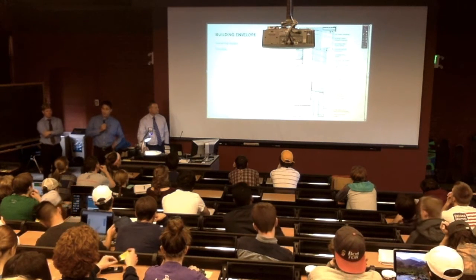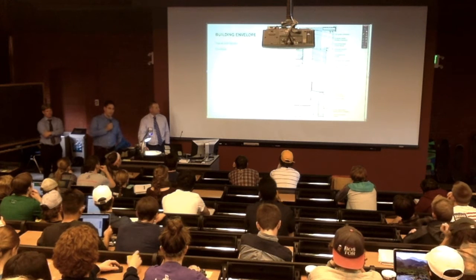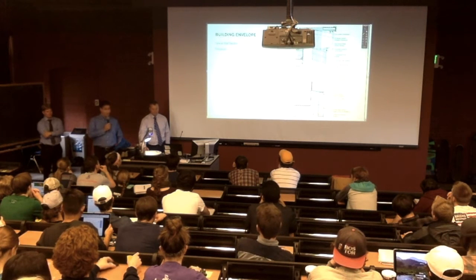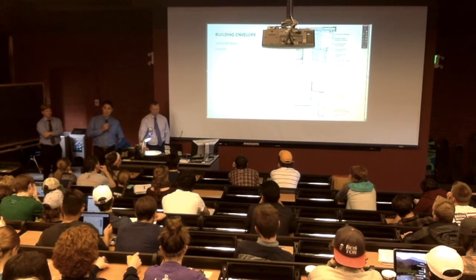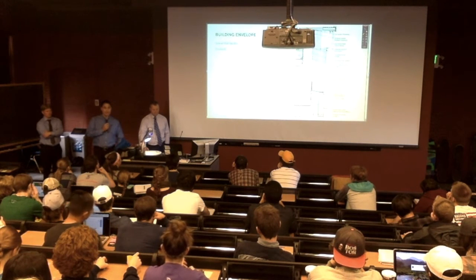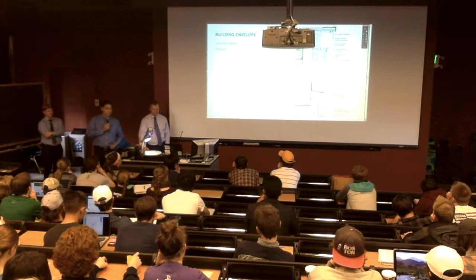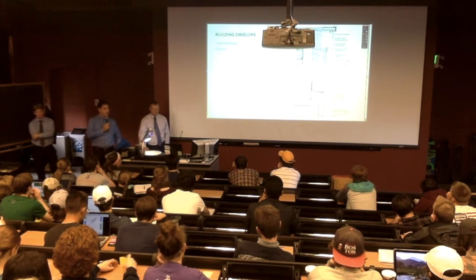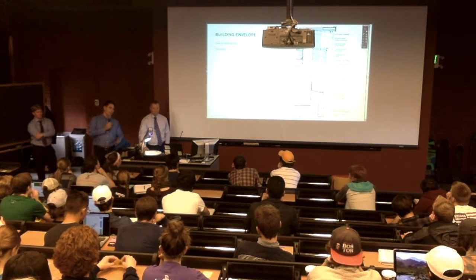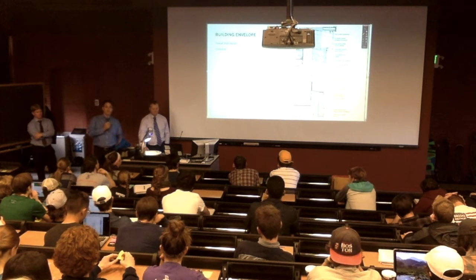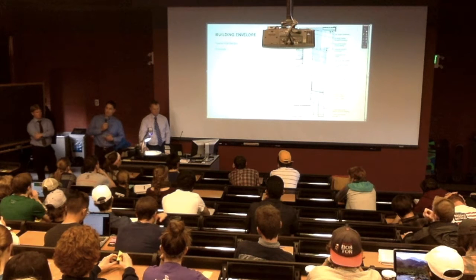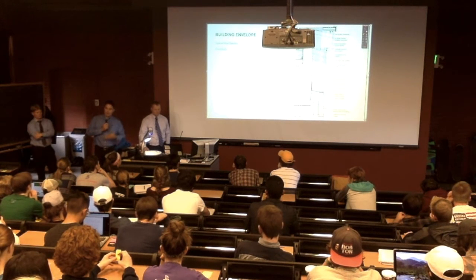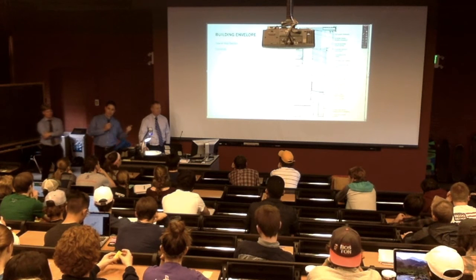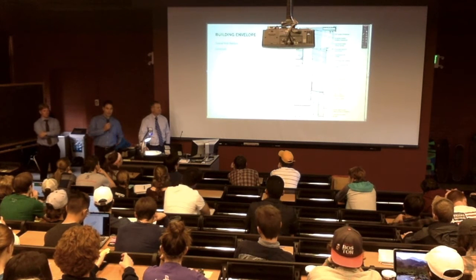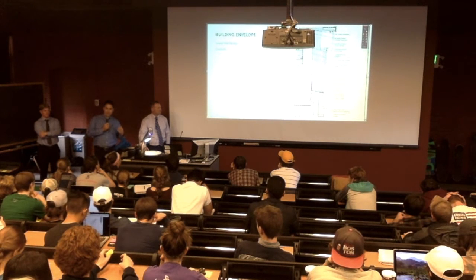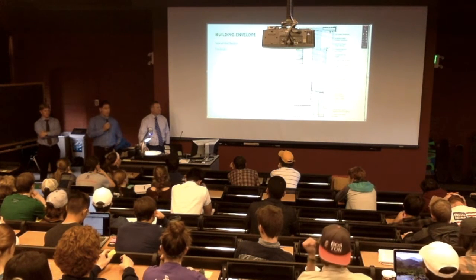Thought that'd be great. So we looked at doubling the amount of insulation on this building. And Bryan called up and said, all right, I just plugged in the double digits here for insulation, and it's not doing a thing. So we were ready to follow what we've been doing on a lot of projects, but it did not apply at all to a laboratory building because it just exhausts all this outdoor air. And the energy model was enlightening because it said you need to put your investment into an energy recovery system like Allan was talking about that recaptures that exhaust air and that energy and heat in that air and puts it back into the building.